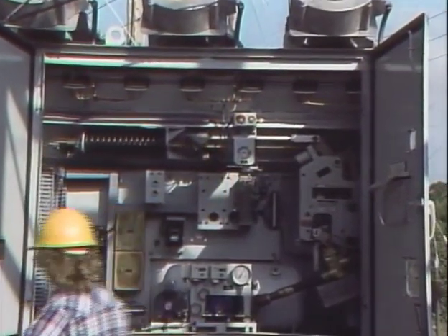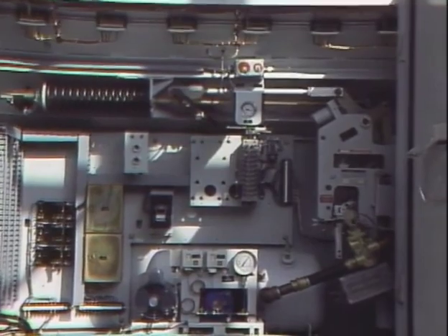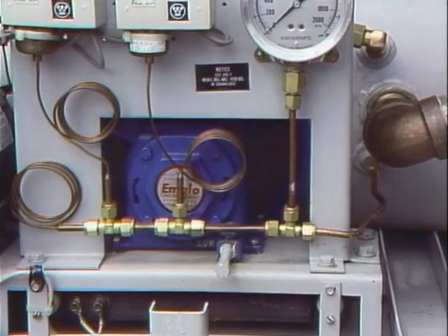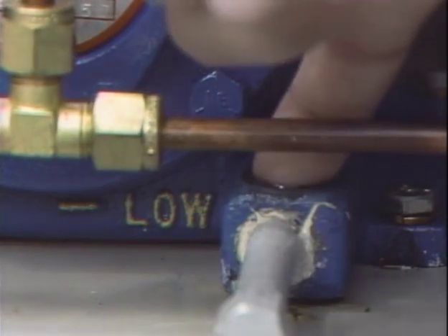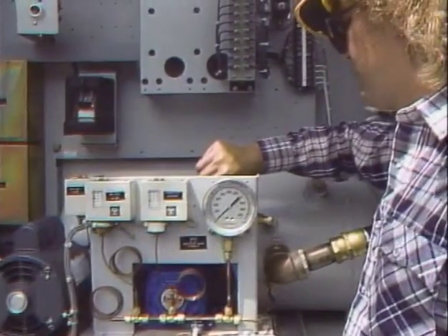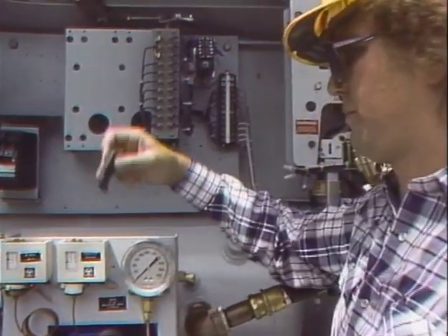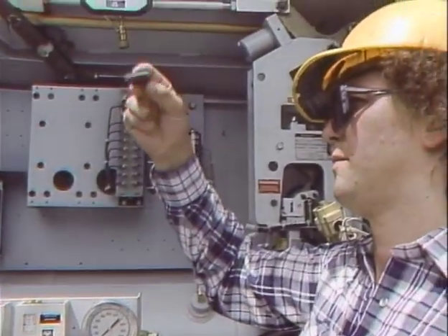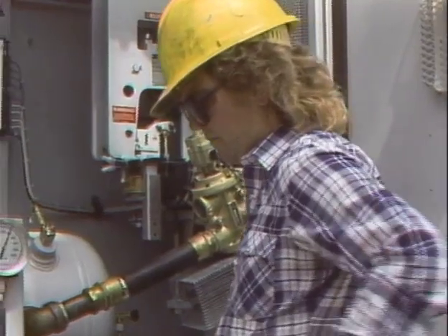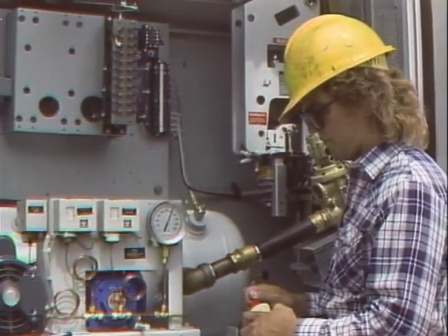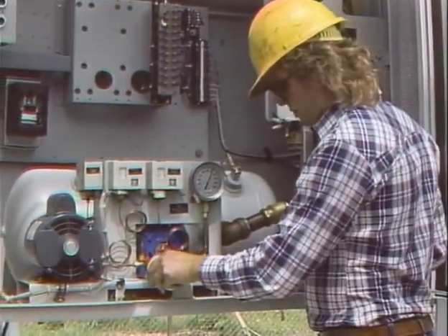Some operating mechanism checks apply only to a specific type of operating mechanism. For example, the compressor on a pneumatic operating mechanism is checked for proper oil level. It's also checked to make sure that the air filter is clean and properly installed, and that the compressor drive belt isn't damaged and is adjusted for the proper tension. The air supply system in the pneumatic operating mechanism is checked for leaks.